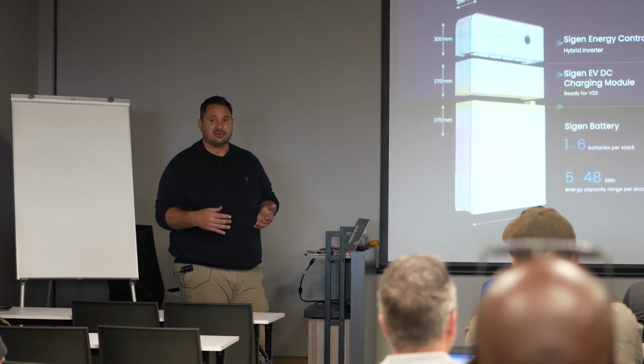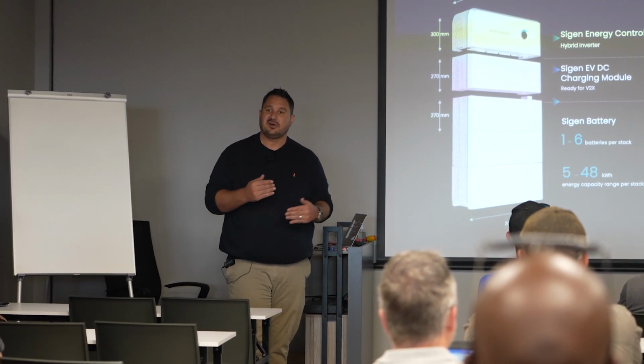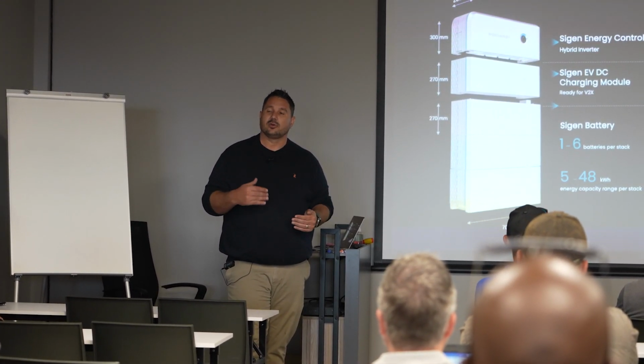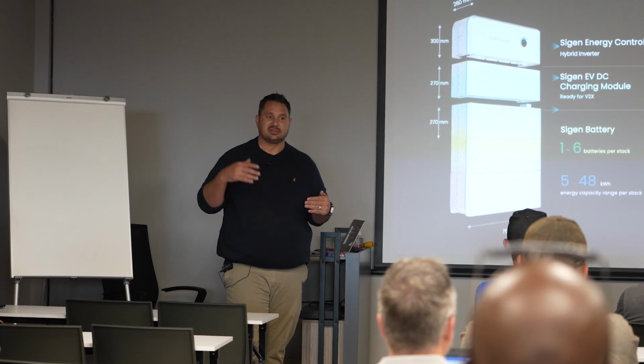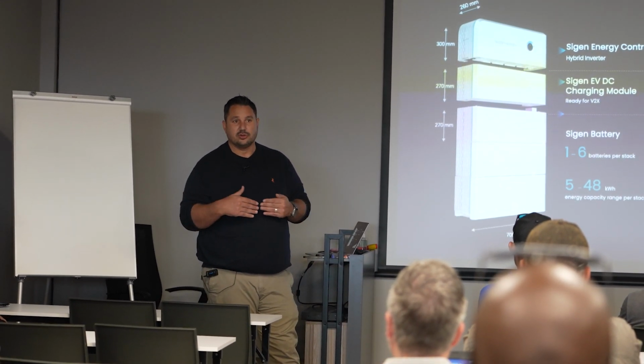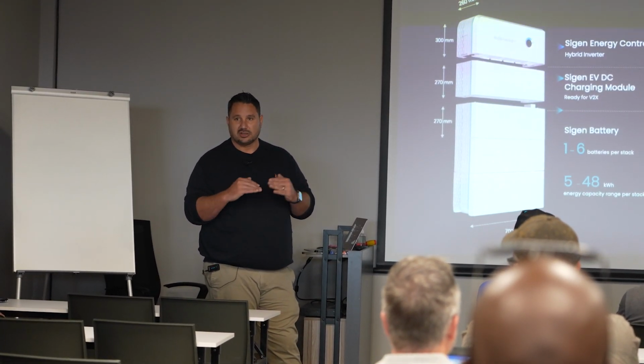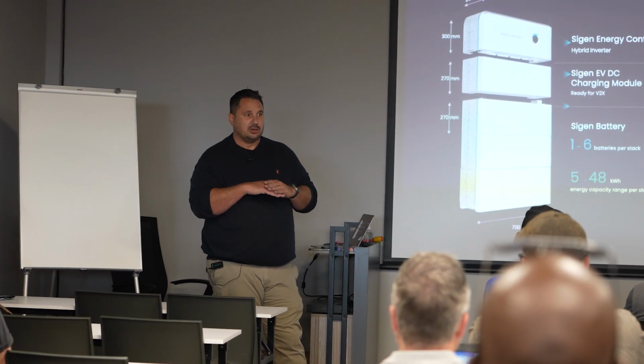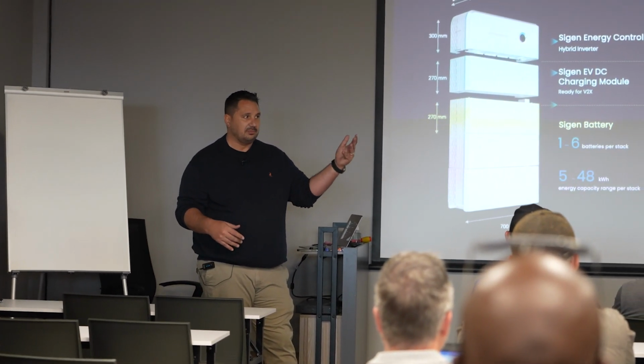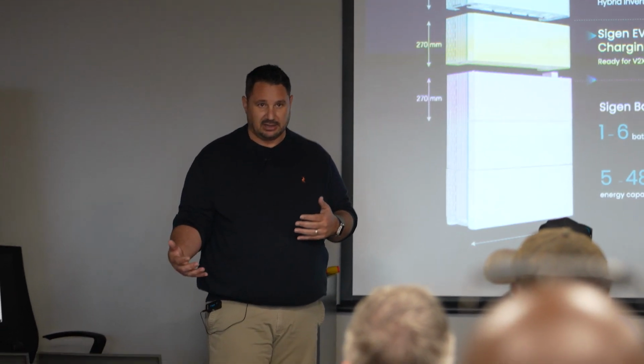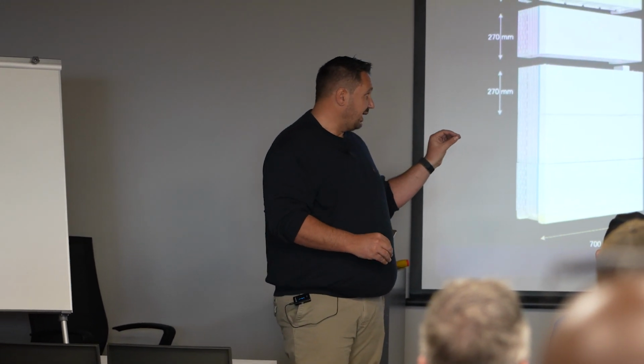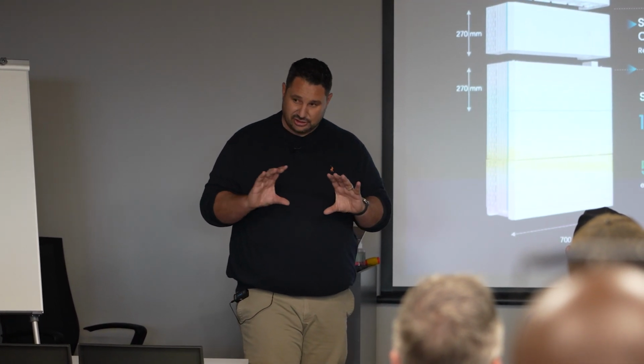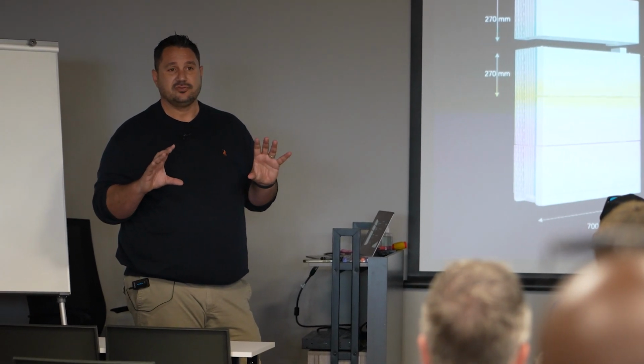So again, with the batteries, same story. You can mix and match 5s and 8s and 10s together. You can also mix and match 1-year-old batteries with 10-year-old batteries. They do not affect each other. There's no cask effect. There's no watering down, where the newer battery gets pulled down by the older battery. Because of the way the architecture works, each single module and each inverter runs on its own. So it's like different devices, and all of them work under their own conditions.